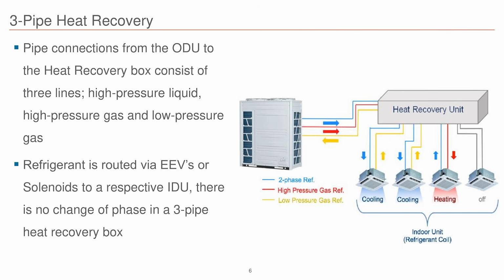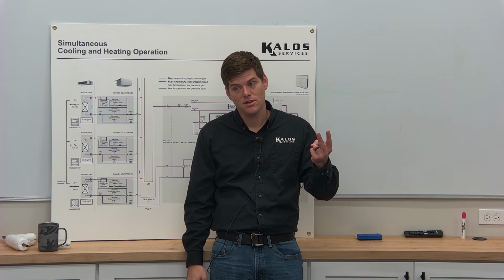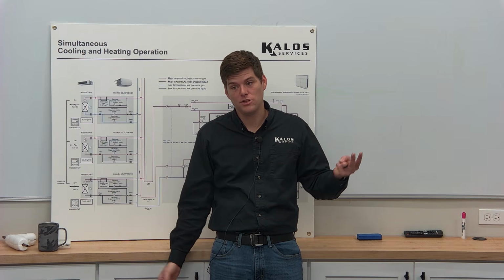So 3-pipe. You'll notice here on my pretty little animated slide, you've got 3 refrigerant lines. It's nothing new. There's no mystery gas in that third line that no one knows about. It's just hot gas, right? So you've got a dedicated liquid line. You've got a dedicated suction line, and you've got a dedicated hot gas line. On a 3-pipe heat recovery system, when it's in 100% cooling, it's just 2 suction lines. So those 2 lines are always being used. It just depends upon the mode.